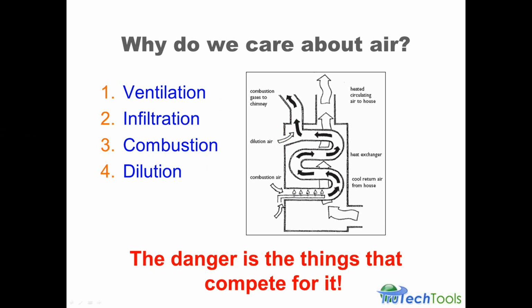We did get a question here: when I'm testing an oil stack for soot, should it be sampled right on startup or should we wait 2 or 3 minutes after startup? Best recommendation I have is you wait until you're at steady state. So you'd be measuring the stack temperature, and that may be about 2 or 3 minutes after startup, but you want to measure the stack temperature and make sure everything is normalized. At startup, you will get a big burst of soot because the combustion system isn't stabilized. But think about for how long is the system running on startup and shutdown over the time it's running in steady state mode. It's the longer amount of time in steady state mode, and that's the right time to take the measurement to get an overall system number.